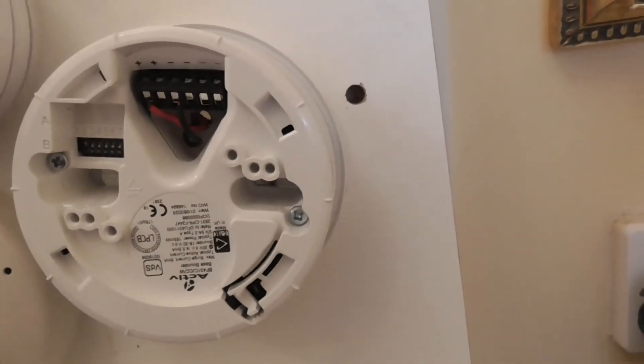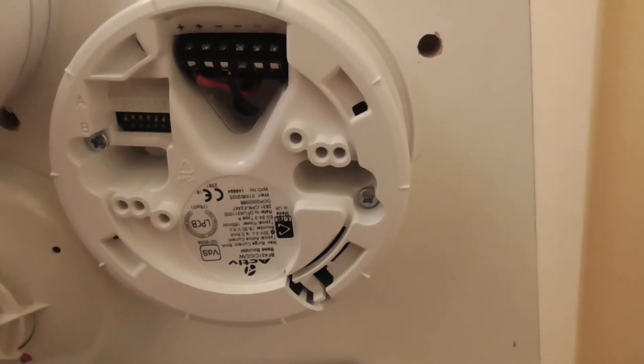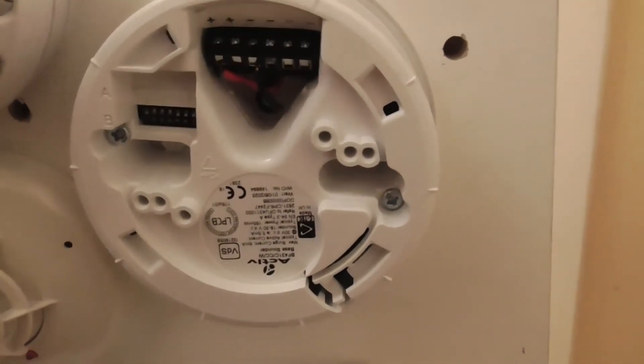Next we're going to do the Hochiki fully-on alternating tone. I'm going to change the dip switches into the Hochiki fully-on alternating tone setting. We're now going to test the CTEC active sounder for the Hochiki fully-on alternating tone, so here we go — turning the switch on to hear the tone.